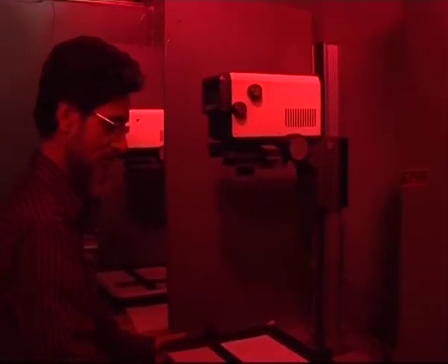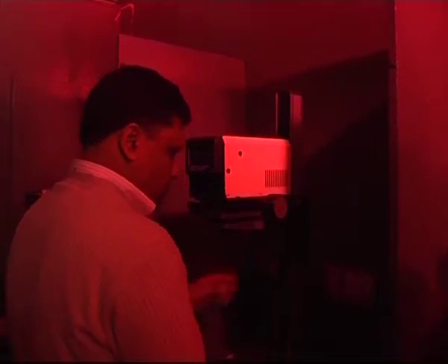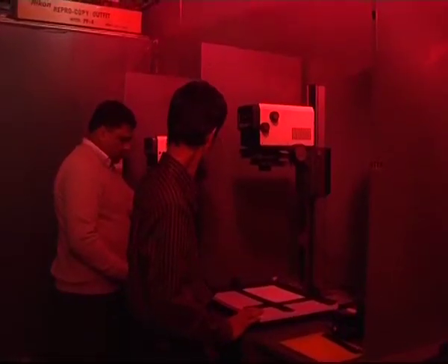Safe lighting. Dark rooms in which film is loaded into cassettes and transferred to processors are usually illuminated with a safe light. A safe light emits a color of light the eye can see, but that will not expose the film. Although film has a relatively low sensitivity to the light emitted by safe lights, film fog can be produced with safe light illumination under certain conditions. The safe light should provide sufficient illumination for darkroom operations but not produce significant exposure to the film being handled. This can usually be accomplished if certain factors are controlled. These include safe light colors, brightness, location, and duration of film exposure.